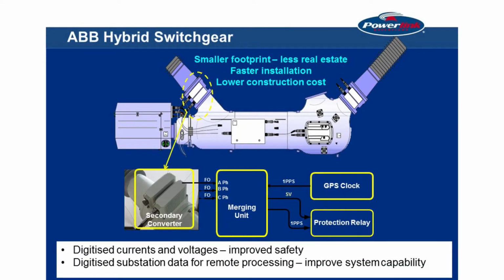We introduced our hybrid switchgear around the early 2000s, and it allowed a number of things. One was to reduce the footprint, the size of the substation, but also allowed us to get an awful lot more data from the switchgear - looking at SF6 gas density, travel times on the circuit breaker, providing a lot more condition monitoring than we had previously. It also had fibre optics to the demountable, allowing some cost savings by reducing copper wiring. But the main thing was that's where the strategy started.